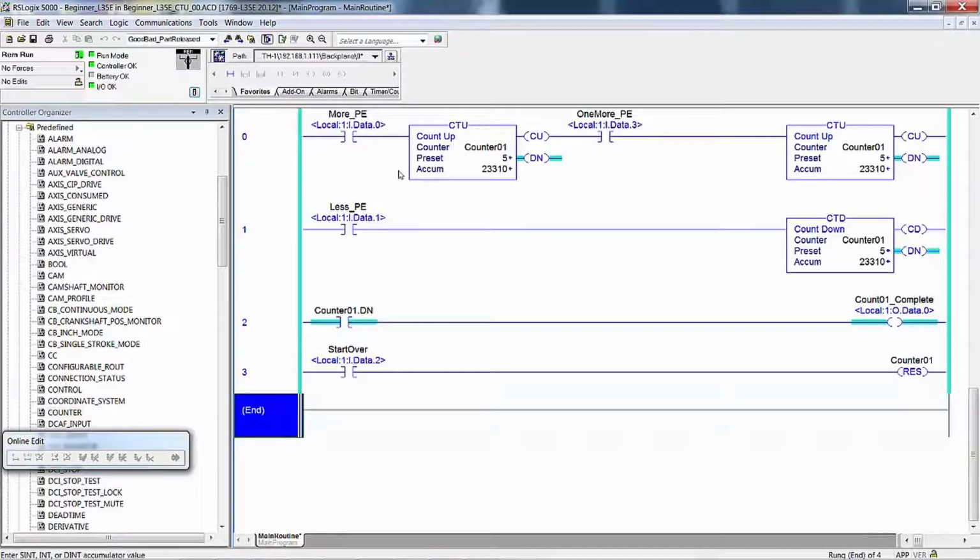This is false, and this is true when we push the button. So if I flip that switch on and leave it on, which I can do with this simulator, you see what it's doing? It's basically scan counting. So this true out initiates a count up bit, but then this is false. The false execution resets this. Next scan around, this is true, counts. False, resets it. So this rung is resetting this counter. It's resetting the false to true state, not the count value.